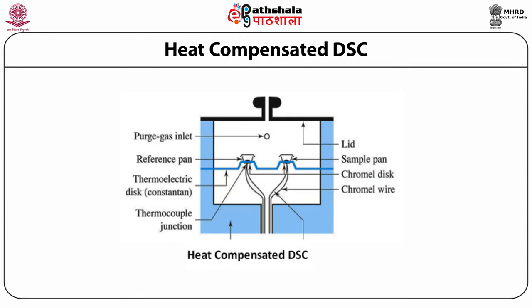Therefore, the total heat flow is equal to the sum of two terms: one related to kinetic response and the other related to heat capacity. In the basic instrumentation diagram of heat flux DSC, the reference pan and sample pan are in the same chamber — the left one is the reference pan and the right one is the sample pan. There is a purge gas inlet, a thermoelectric disc made of constantan, and a chromel disc. Chromel wires are connected to form thermocouple junctions at the end points of the reference pan and the sample pan.